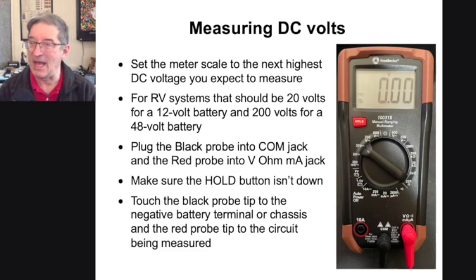As before, you want to make sure you set your meter scale to the next highest DC voltage you expect to measure. Most of these meters will have something like a 20 volt scale, which should be sufficient for testing 12 volt batteries. However, you'll be encountering 48 volt battery stacks, and you can no longer use the 20 volt selection. For that, you've got to bump it up, probably to the 200 volt scale.